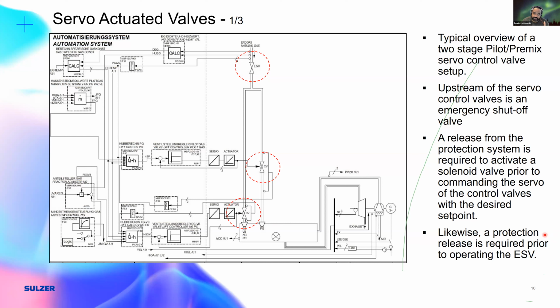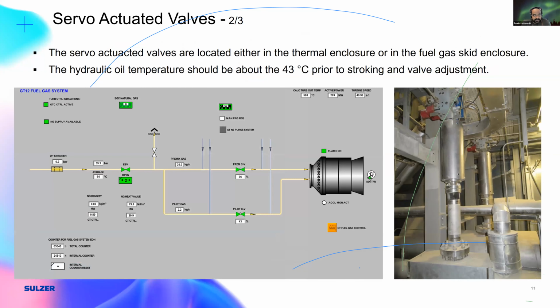However, during switchover, I have to be sure I do not exceed emission requirements, because the power plant can get penalized. And when they do, it usually comes with a fine that they have to pay, or they can have their license revoked. Now, I will go on to the next slide, which gives us a view of the valves. So this, for example, is the pilot gas, and the other valve in the background is the control valve for the premix line. And this is how it would look on the HMI.